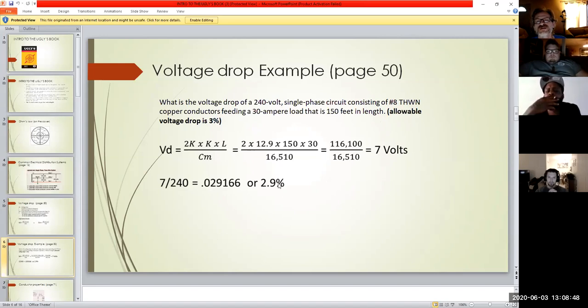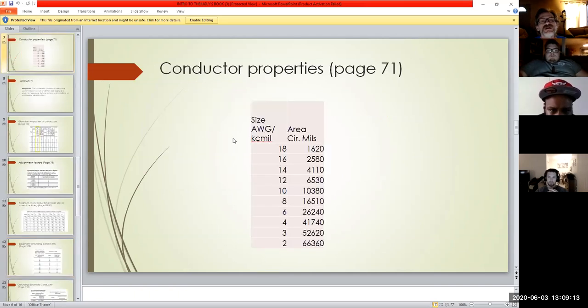That loss comes out to about 2.9%, and I'm allowed to lose up to 3%. Anything over 3% and I have to go to the next wire size up. So this one just makes it at 2.9%—that's just an example, but it's all in the Uglies book, and that's why this thing is awesome. You literally have this right there, you just need to know where to look it up.